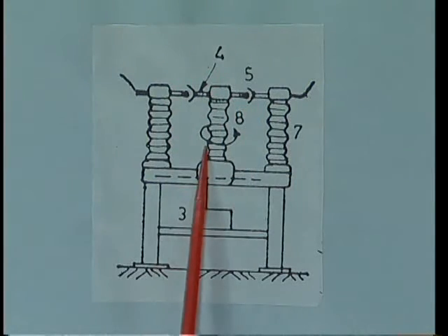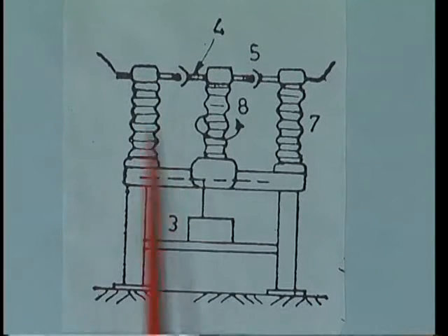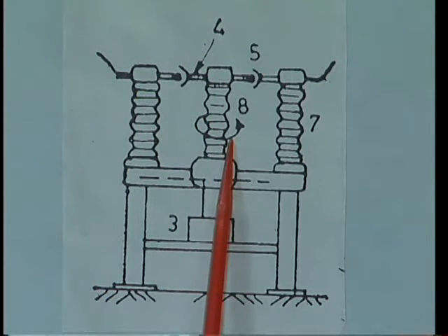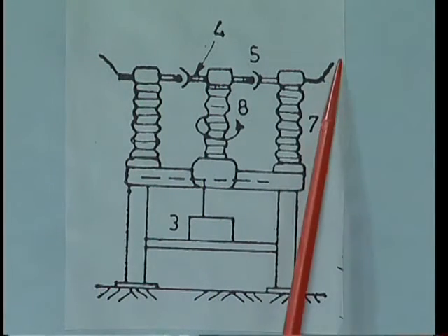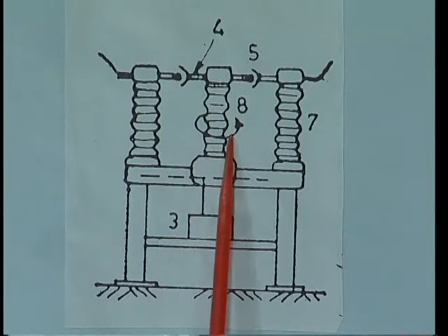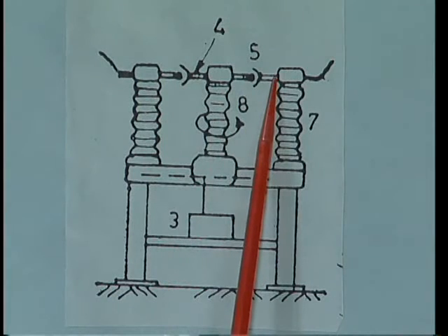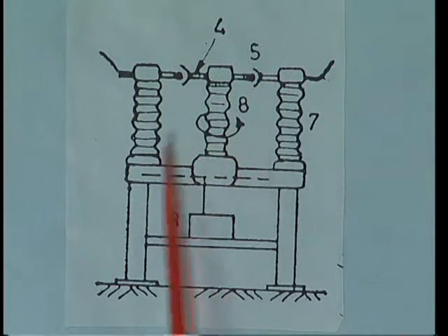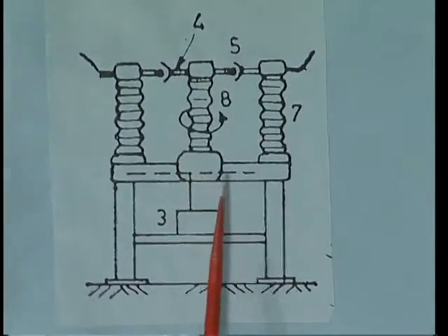The double break isolator has two fixed insulator posts on either side and a middle insulator that rotates. It is connected to an operating handle system and can be used for two-way connections or single connections. Only the middle insulator moves vertically while the two outer ones are fixed. When it moves and makes contact, isolation also takes place here. This double break isolator is used for 220 kV or 400 kV substations.